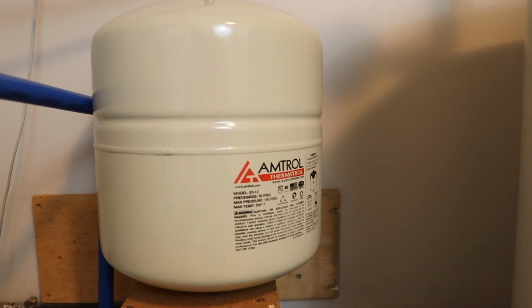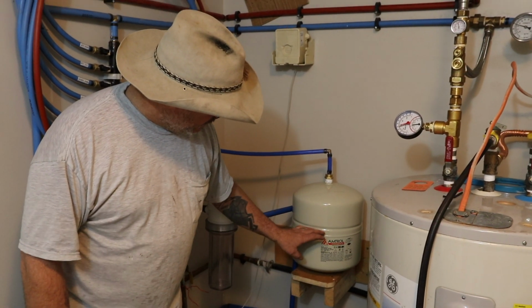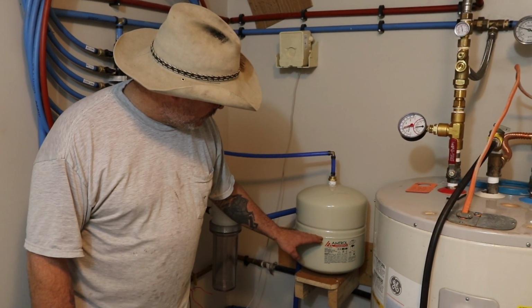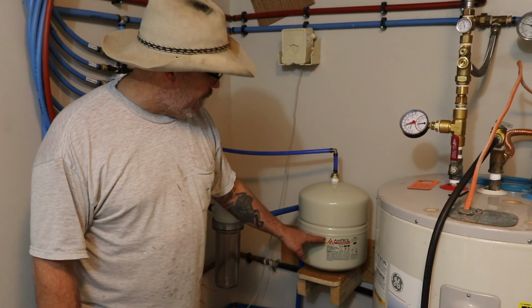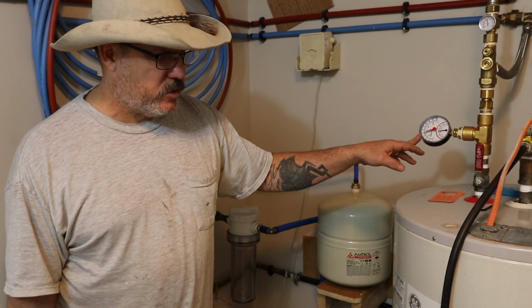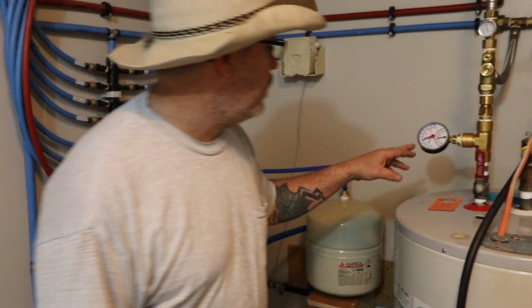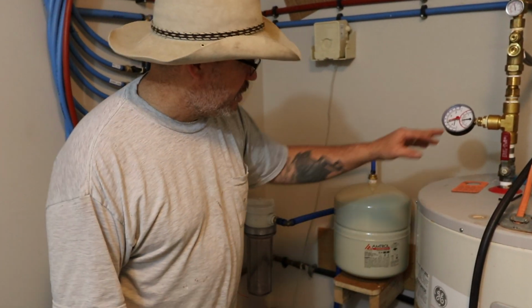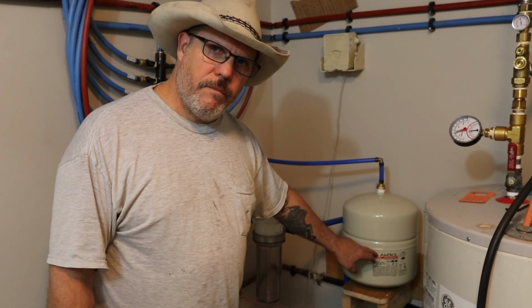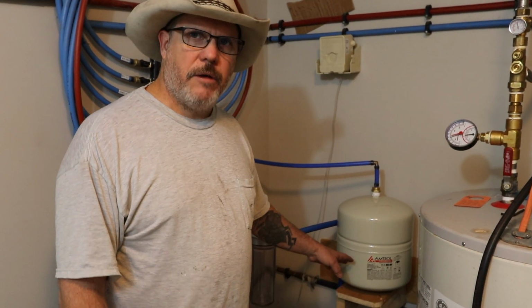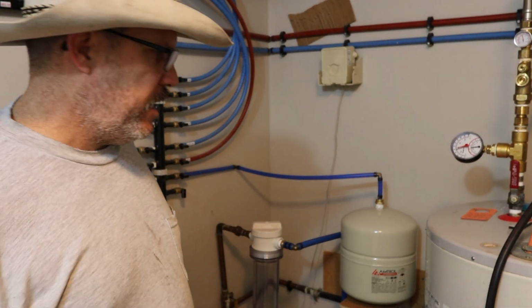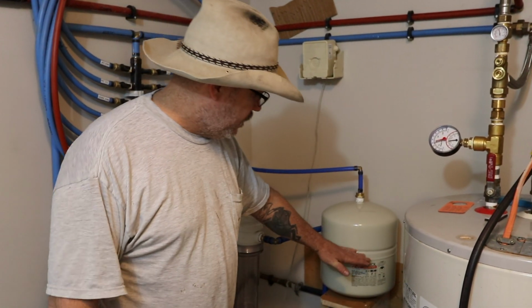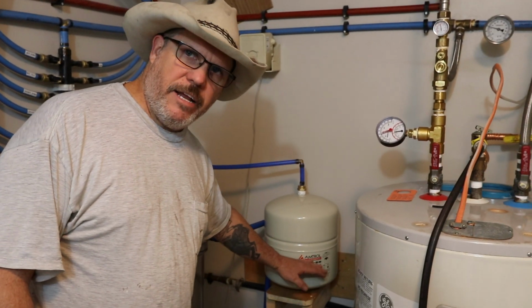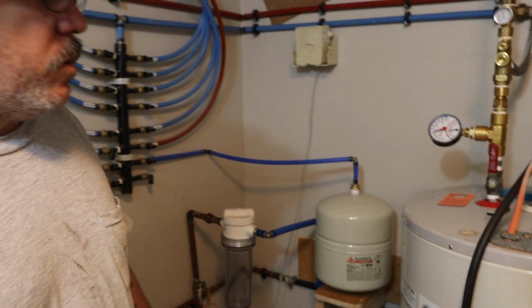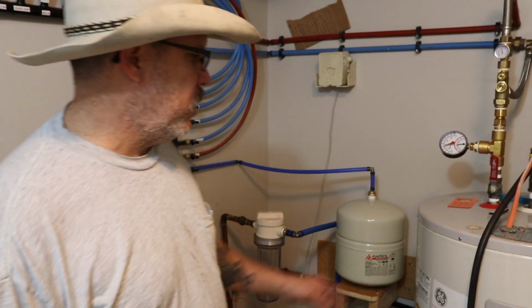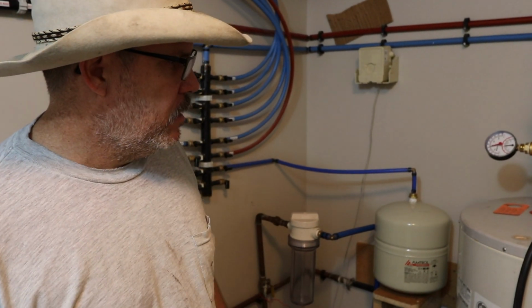Basically, I've got cold water in here, about this much, and then I've got a diaphragm in here, and I've got air, and I match that air pressure with what my max pressure would be, which is about 80 psi. 76 to 80 psi, I think it's about 76, and that's how much air pressure I put in there, and then it maintains. If I end up building too much pressure in here, it just pushes down on that air. Air is a lot easier to compress than water, so I don't have an overpressured system.